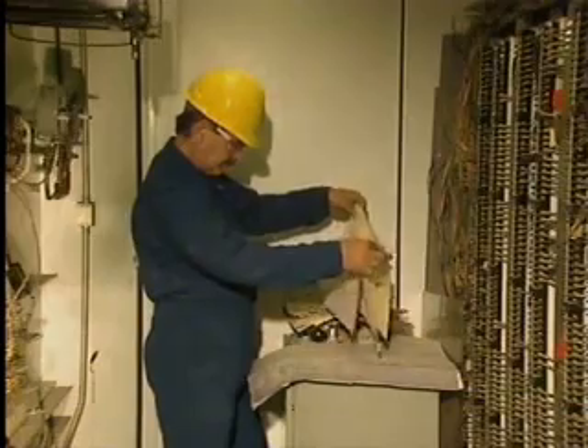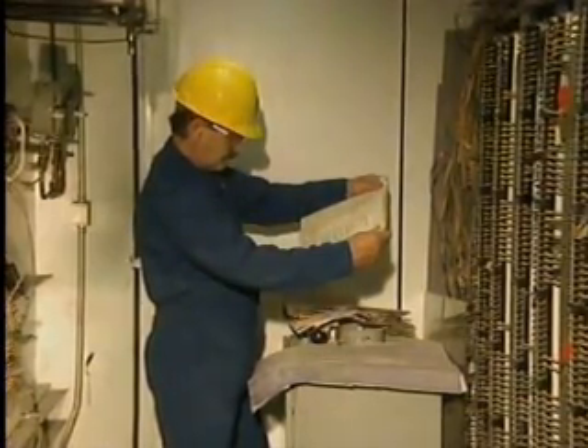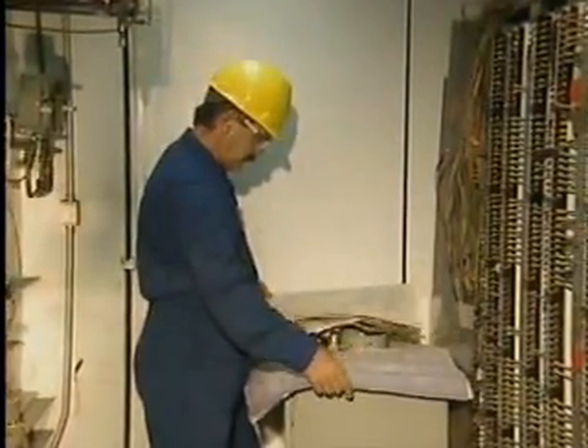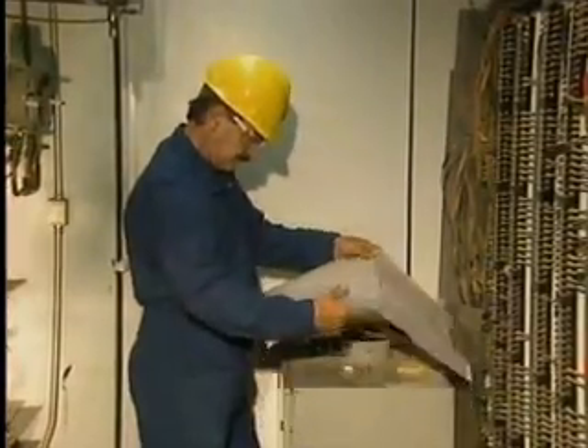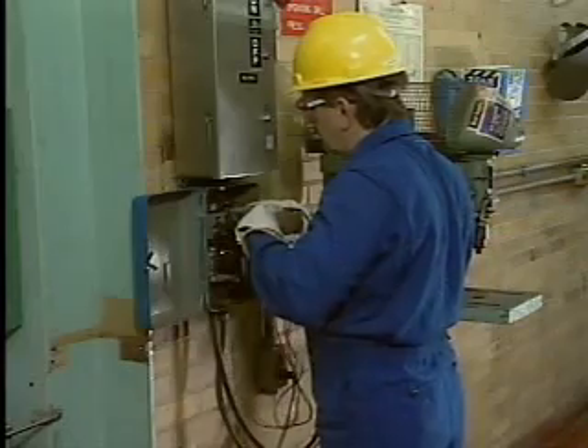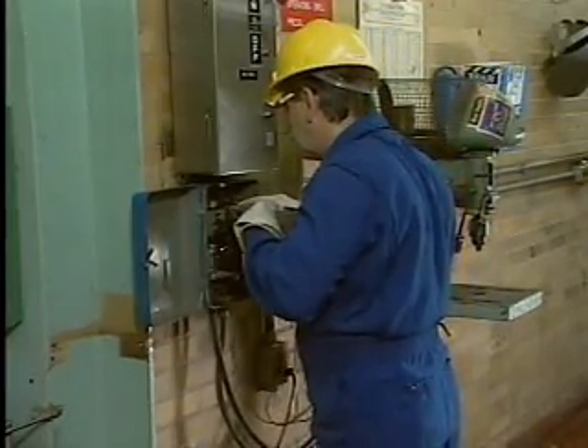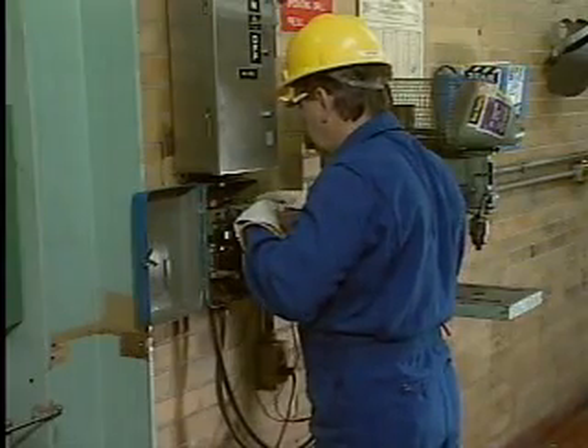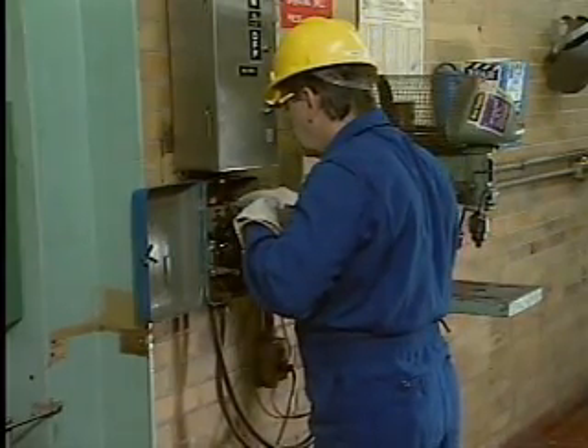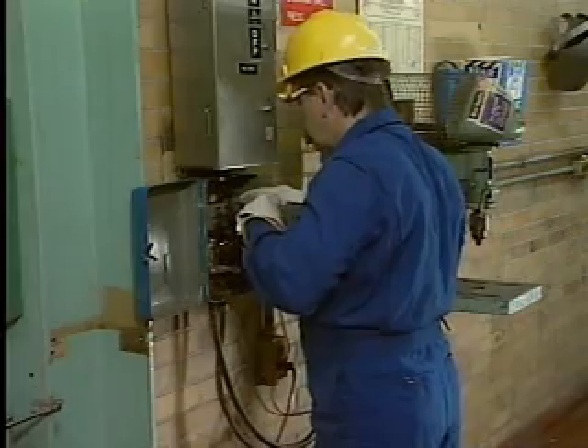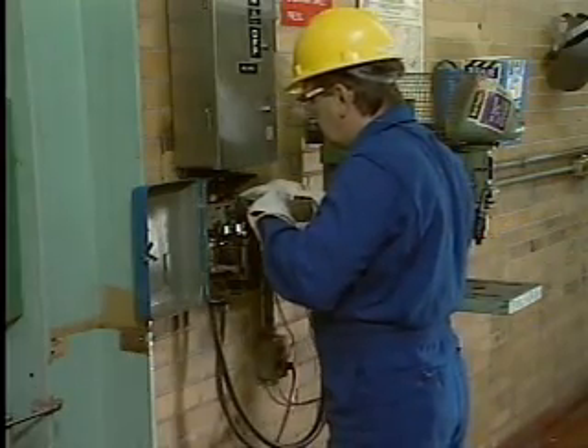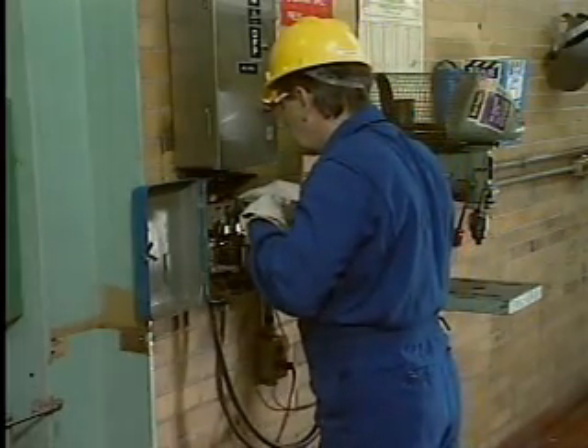Troubleshooting is usually based on a process of elimination, that is, separating the factors that are not causing the problem from factors that might be causing the problem. Electricians commonly separate these factors by making voltage checks. Voltage checks can be made with a variety of testing devices. In this unit, we'll use a multimeter that's been set up to function as a voltmeter.